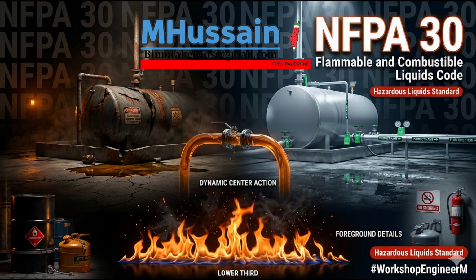Hey, just to be clear for you listening, when we say water sprinklers for industrial liquid storage, we are not talking about those little recessed heads in your office ceiling. Oh, absolutely not. The code demands massive density requirements based on the liquid class, the container type, rack height. I'm seeing design tables requiring delivery densities ranging from 0.21 gallons per minute per square foot all the way up to an astonishing 0.60 GPM per square foot.